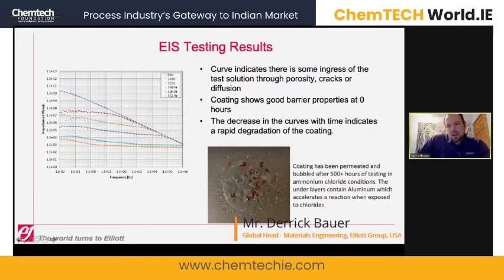The industry standard coatings rely on an aluminum-filled chromate phosphate undercoat for the corrosion resistance, and this does work well in hydrocarbon fouling. For ammonium chlorides, the chlorides react readily with the aluminum, especially with the steel substrate behind it, and that leads to increased corrosion whenever the top coat is penetrated. The PosiCoat Protect does not rely on any sort of aluminum or undercoat to provide that corrosion resistance.